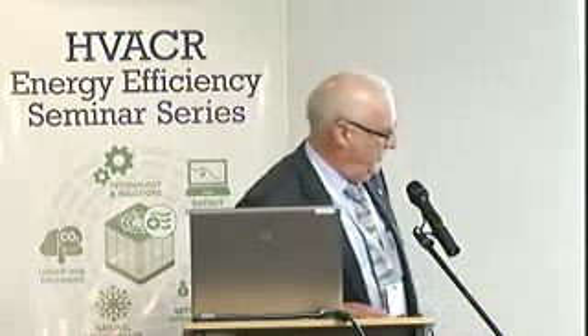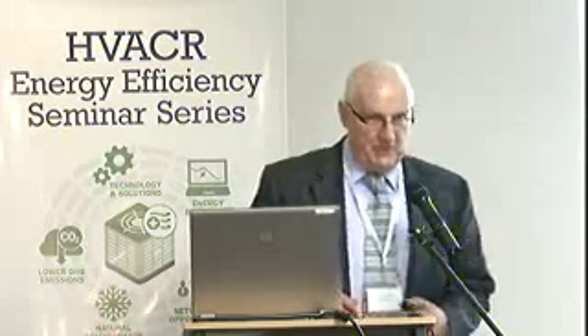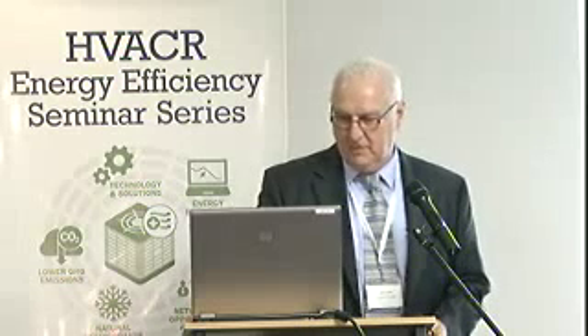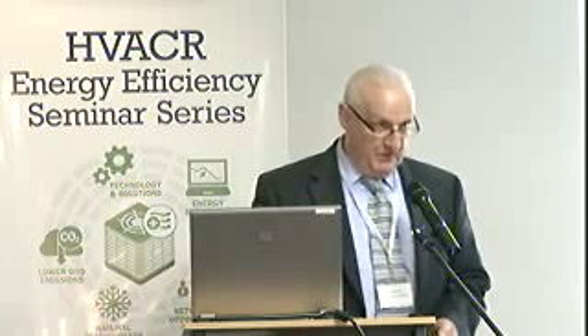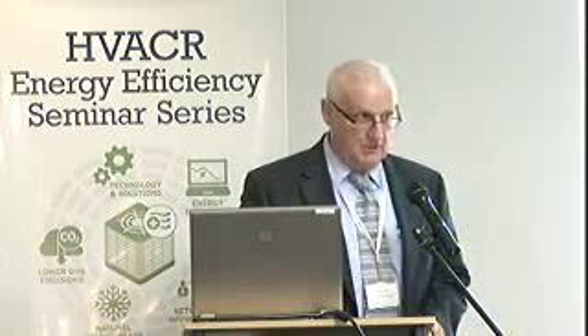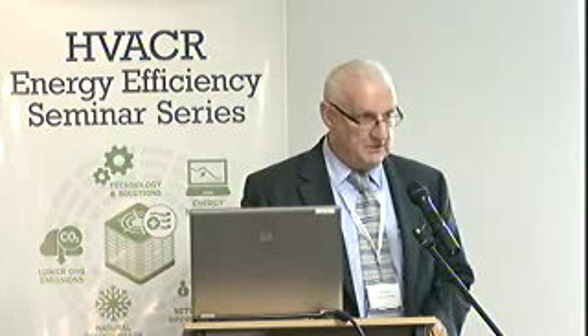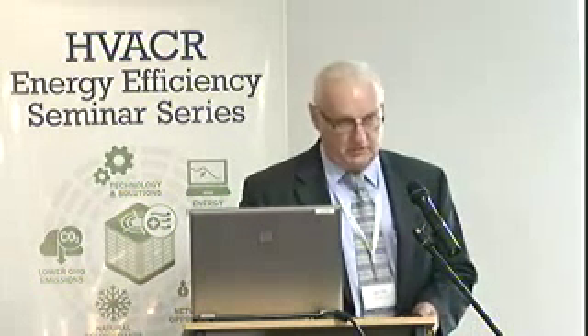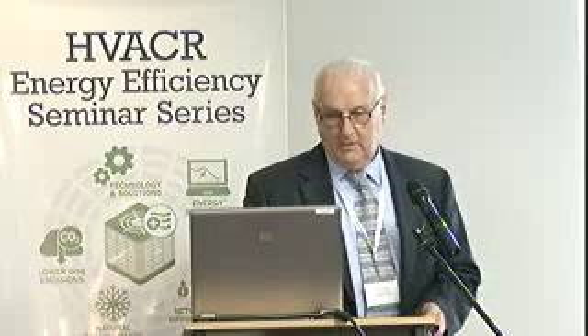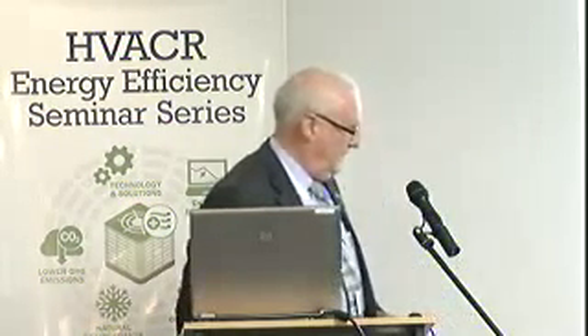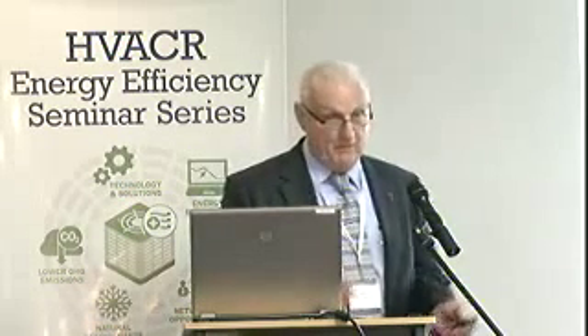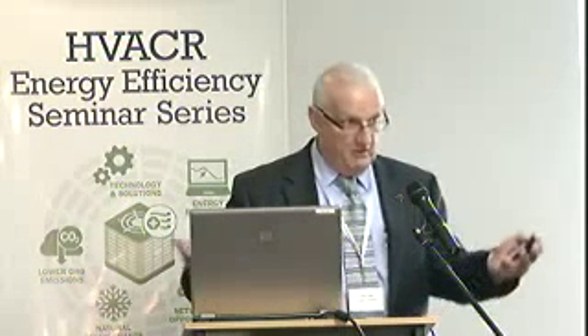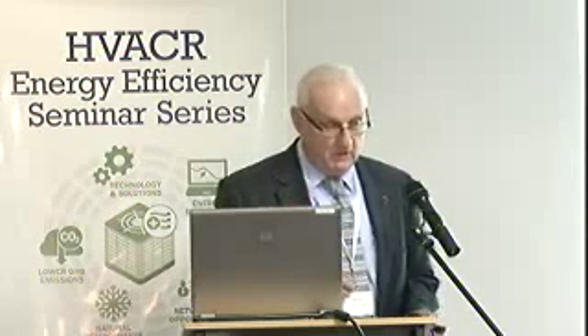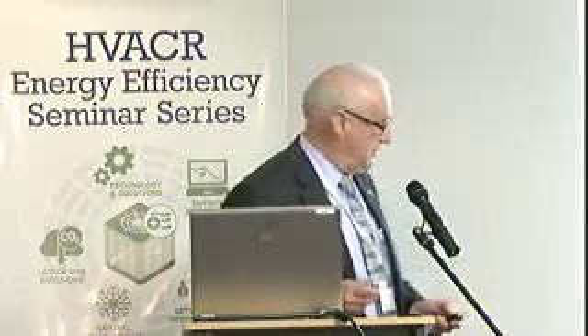I mentioned before NEMA and the plus or minus 10%, but they also stipulate that the limit to unbalanced voltage they would recommend is as low as 1% between phases. Your supply authority typically is looking at 2%. Now, I know this is a little complicated, and I'm going to go to a simpler one in a moment. This is in my paper, and I'm more than happy to send it to any of you if you'd like to give me your information later on. I can email this through.